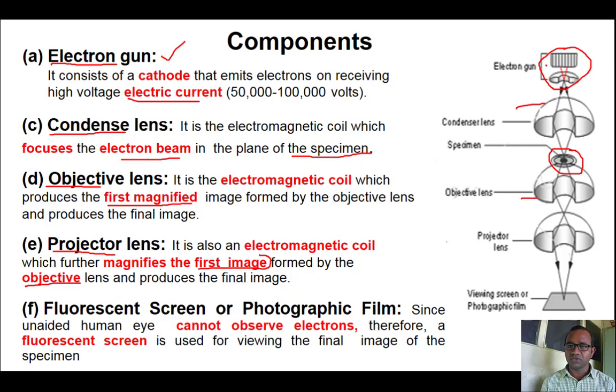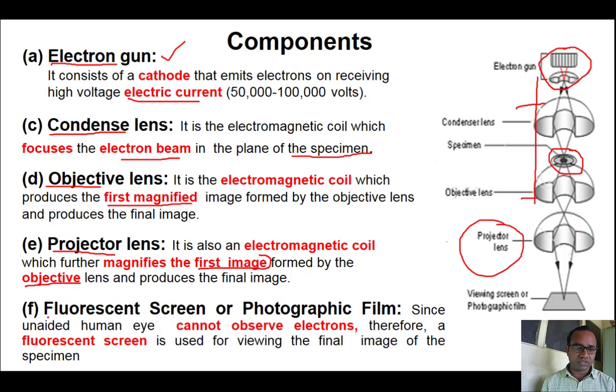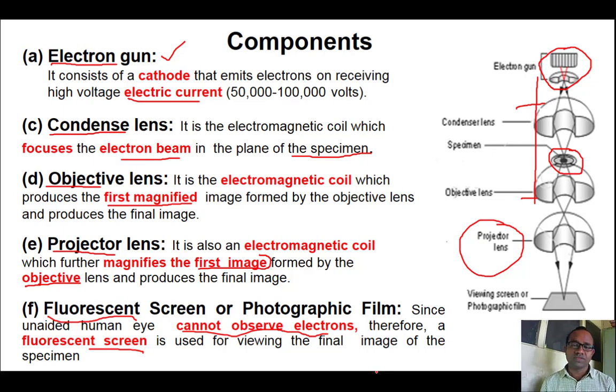Electrons produced by the electron gun travel and fall onto the sample. An important point is that we have to create and maintain a vacuum inside the whole structure because the movement of electrons will be deflected by air. The electron travels in a straight direction onto the sample in the presence of vacuum. The electrons finally fall onto the specimen, which is then focused by electromagnetic lenses. Since our eyes cannot observe electrons, we need a fluorescent screen to observe the image.